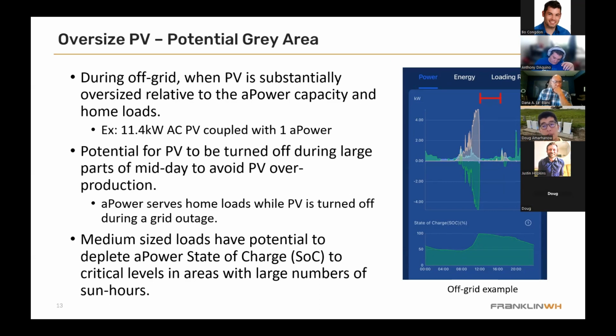There's that famous 11.4 kW SolarEdge inverter that's pretty popular. People will install it, especially if you have net metering, and think, okay, I can make a whole bunch of power and spin the meter backwards as much as possible. Then they want to add one battery to it afterwards. That's not going to be the best case scenario, because for most of the day you're going to have too much PV production, since our charge rate is about 5 kW per aPower plus your home load, which may be an air conditioner or some small loads. So you may have a home load of about 6 or 7 kW. If your PV production is 11 kW and you're off grid, you have about 4 kW of too much power, and the system is going to end up turning off that PV for a portion of the day. You see that in this diagram on the right here.